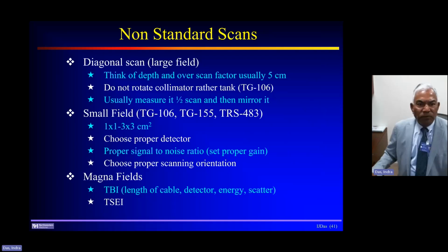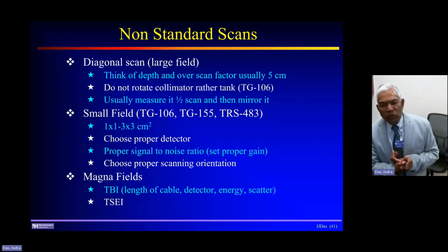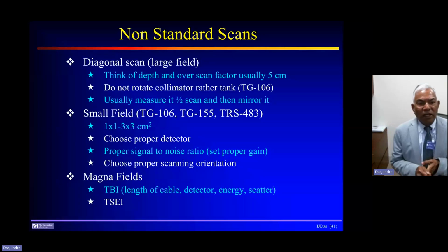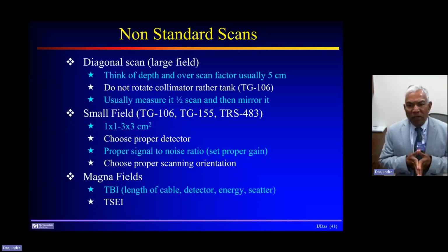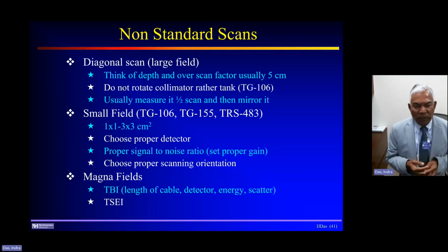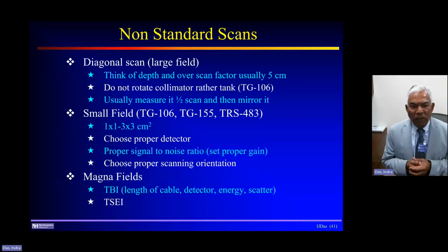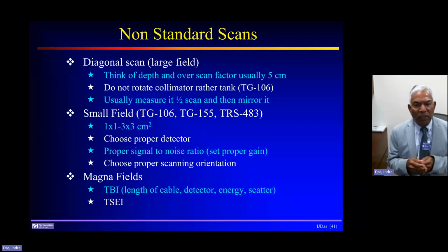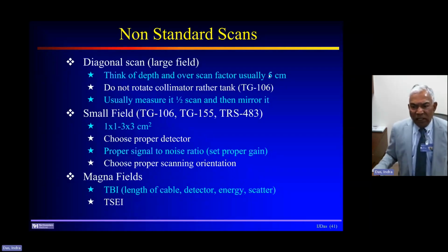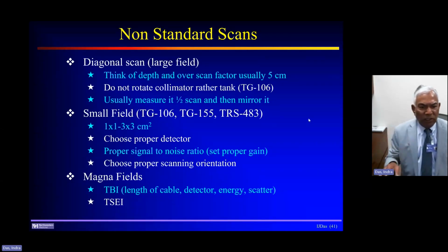Now, there are other things that you need to pay attention to. One is the diagonal scan. Most beam modelings are done through the diagonal scan. In the old days it was very difficult because the software was not robust enough to make a diagonal scan, but now modern tanks can do all that. You could also think about large fields, where you have to have an overscan of 5 centimeters on each side. The tanks may not be sufficient in length or width, so you may have to do a half scan and then mirror it and all that.